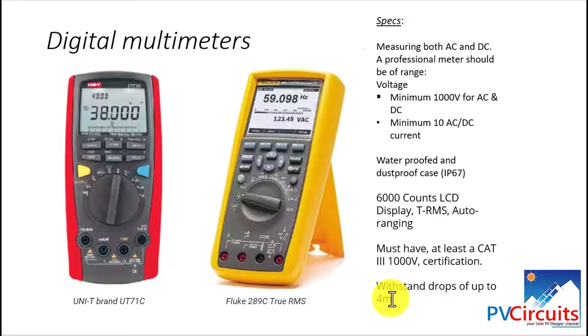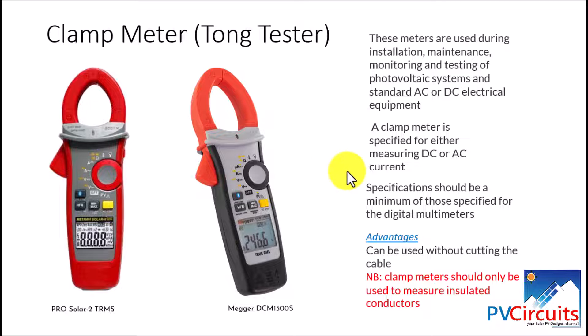Now we look at the clamp meters, also called tong testers — 'tong' because the clamp opens and looks like a tong. We have selected two types of these meters. The clamp meter behaves more or less like the multimeter; however, it has the advantage of measuring electrical properties — voltage, current, and resistance — when the system is running. You can clamp the meter on a live wire to get readings. One key advantage over digital multimeters is that they can be used without cutting the cable; you simply loop it around the cable to get your readings.